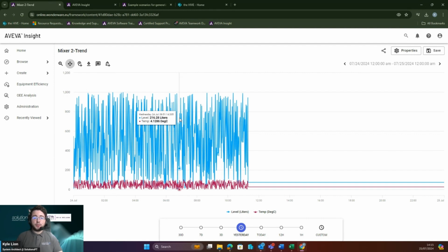And that's been a guide for how to use asset types in AVEVA Insight. We created a single asset type for mixer. We created a single instance of that in mixer 1. We defined a piece of content that we wanted to have every mixer display, which in our case was just a single trend. And then we added two more mixer instances, mixer 2 and 3, to show that that was automatically then created for them. For the sake of video length, I've kept things fairly simple in my examples here, but you can easily follow this process to automatically create tens or hundreds of individual charts, dashboards, condition-based alerts, or analytics models just by creating them once and using this asset types feature.